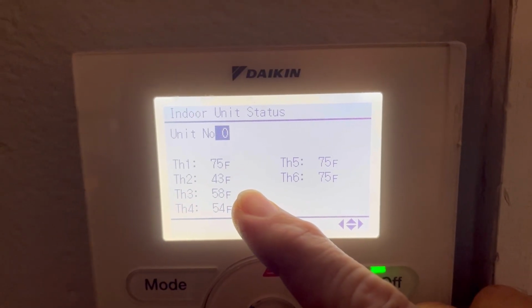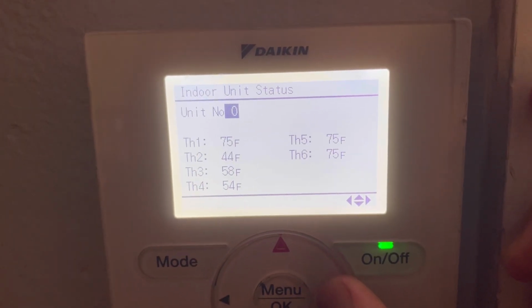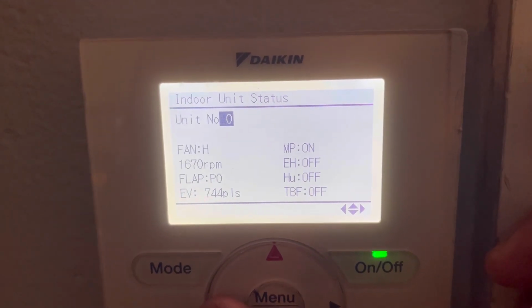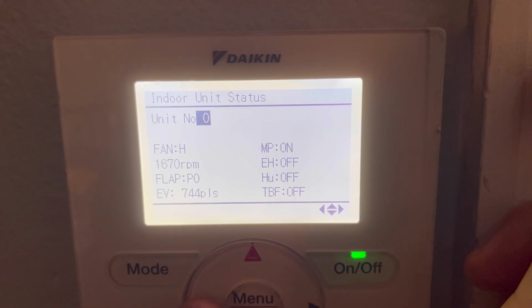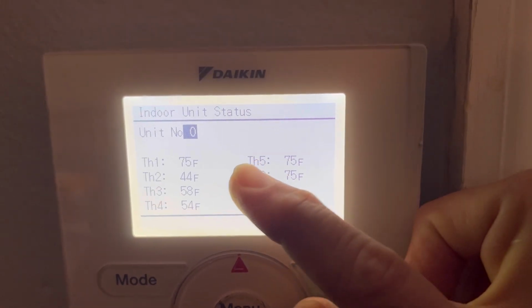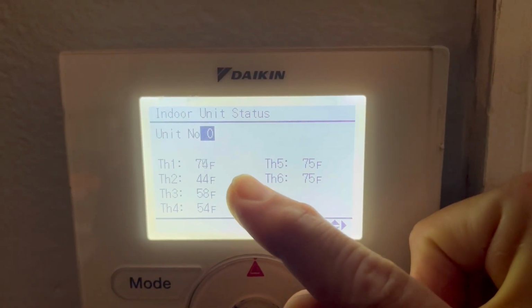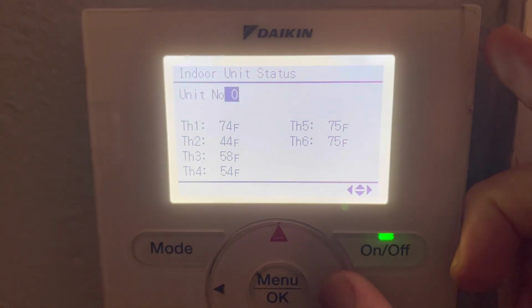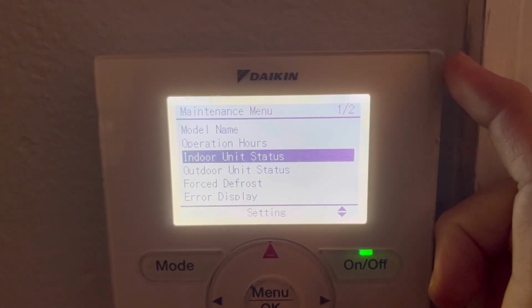Look, 43, 58. Remember, my pulses, they went up, right? They went from 712 to 744, and they're going to continue to go up. And I'm going to watch this superheat climb to 9, right? We want a 9-degree superheat between these two, and then my discharge temp. And so this is why I like the maintenance menu.